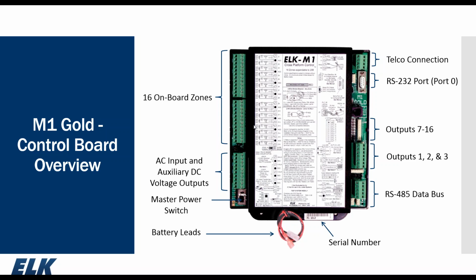The upper left-hand side, the first two terminal blocks, are our 16 on-board zones. Below that is the AC input and auxiliary DC voltage outputs, the master on-off switch, the battery leads. The bottom of the enclosure, there's a white barcode sticker that contains the serial number for the M1. That's a unique number. It's an 8-digit number starting with 0. No two M1 serial numbers have ever been duplicated, and you'll need that information once we get into the RP software in order to connect to the system. You can also obtain the serial number through keypad programming as well.